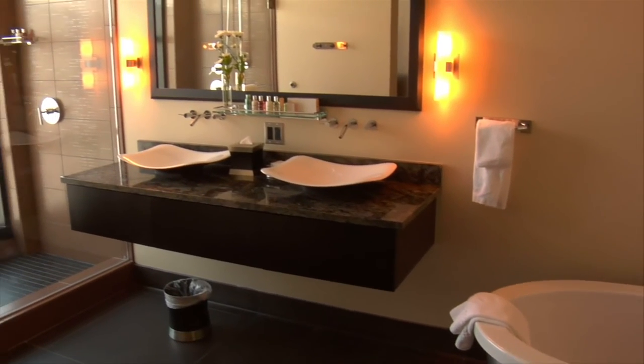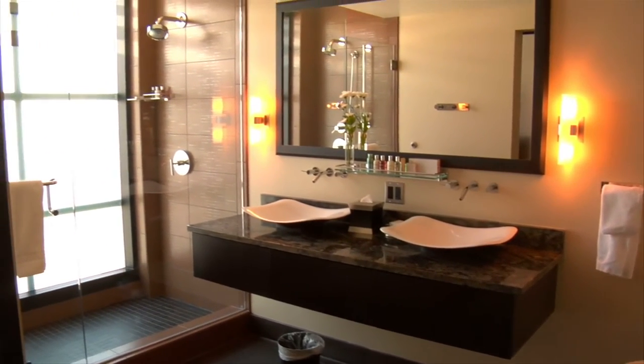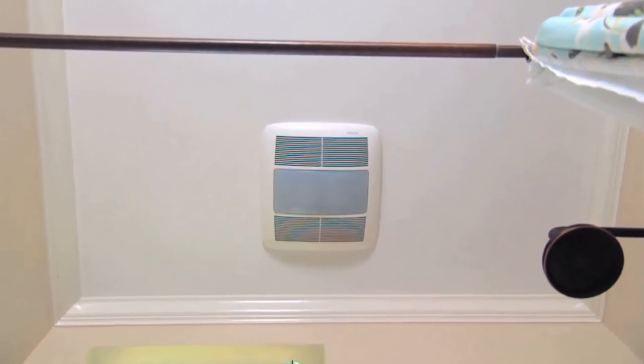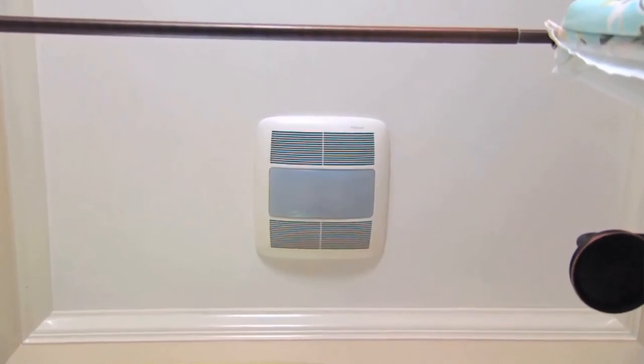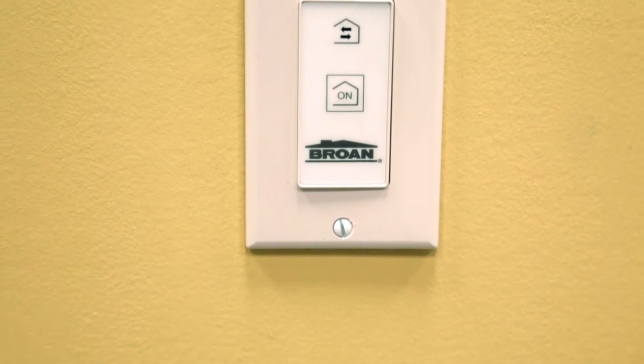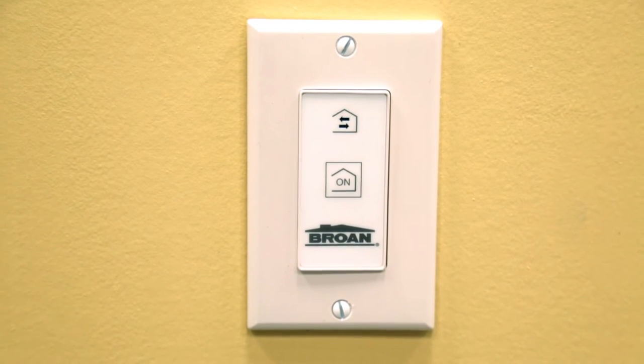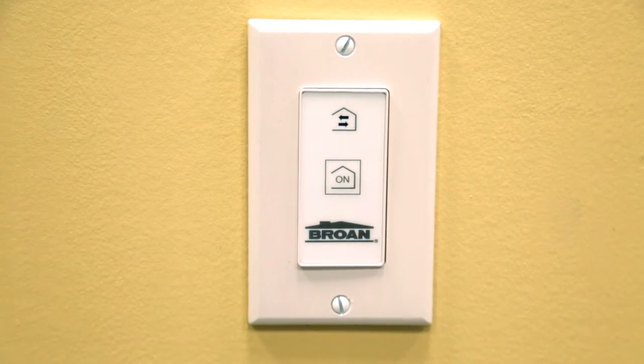When the ERVS-100 exhaust register is located in a bathroom, the product can also replace one bath fan. In this configuration, the unit should be connected to a 20-minute override control in the bathroom. Wire the control switch according to the package instructions.